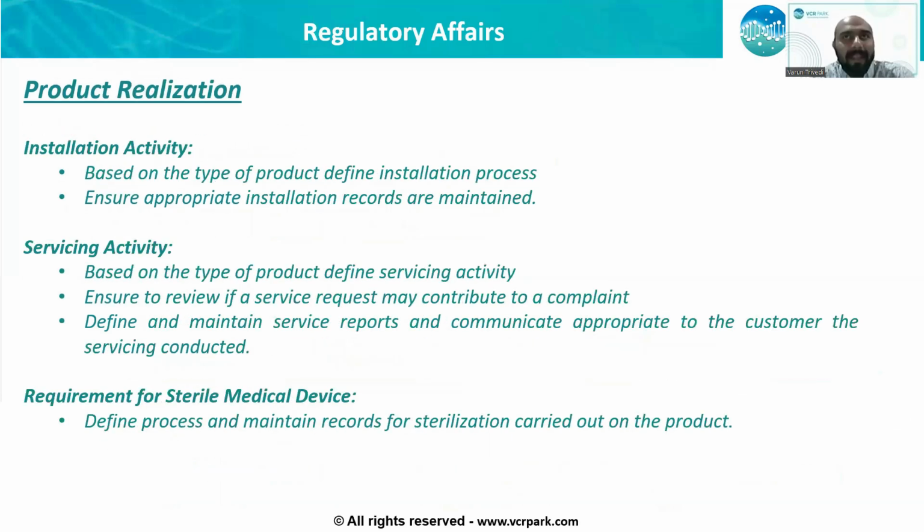Where applicable, if your product is something that needs installation, then you need to ensure that you have defined the installation process. You need to ensure that the process also defines how the installation activity will be captured as part of your installation report. What needs to be in the installation report needs to be defined, keeping the installation activities in mind. It is only when the installation report is signed by your installation engineer and the customer that the installation is deemed to be completed and the product has been transferred to the customer.